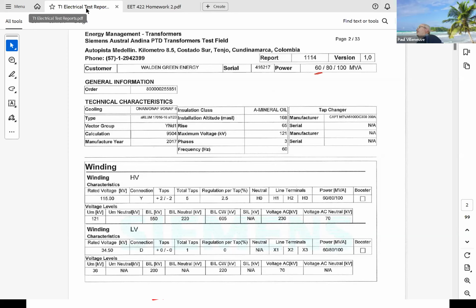Not a trick question. The other test, the short circuit or the open circuit or the no load test. Do you apply all the test equipment to the 115 side or the 34 side? 34.5 side? 34. Why? I don't quite remember. It's kind of that way, but do you think it's easier to buy a power supply that can put out 115,000 volts or 34,500 volts? The lower one for sure. I'm not saying it's easy, but if you got to go out and buy a power supply that can put 115,000 volts and then run the cables and all that stuff and need different insulation, it's much, much, much harder to find a 115 kV power supply than it is 34.5.